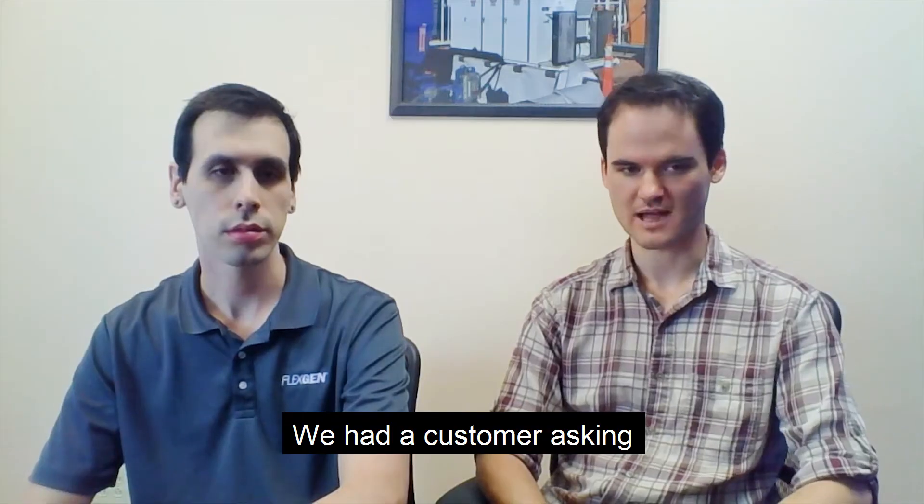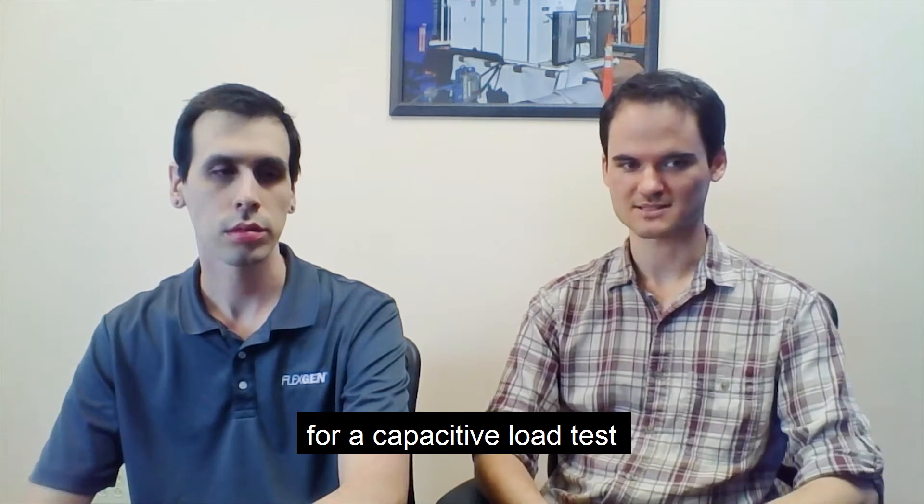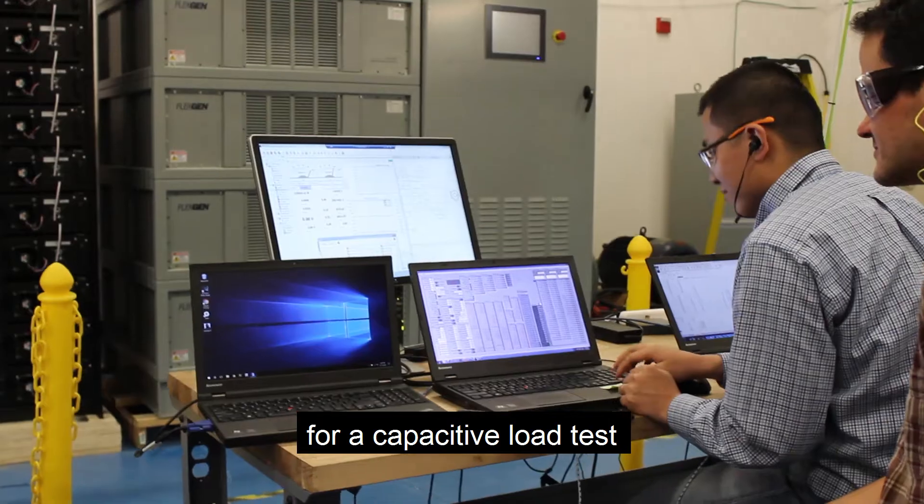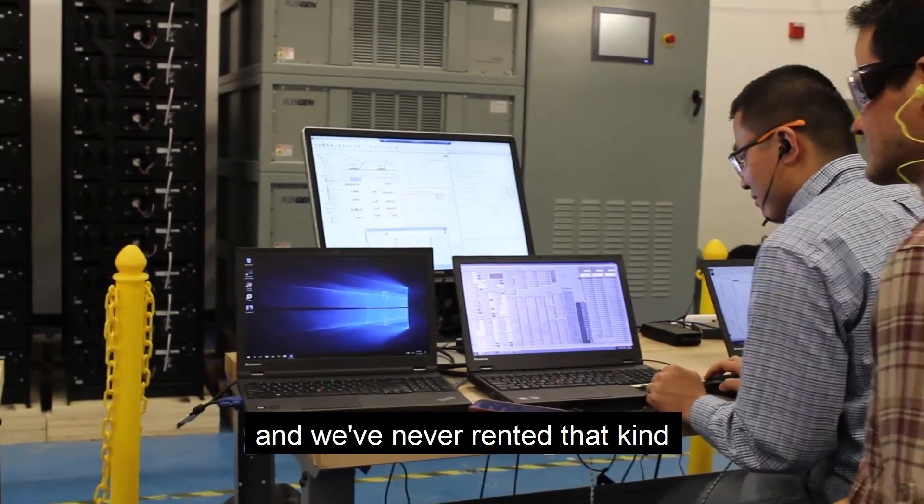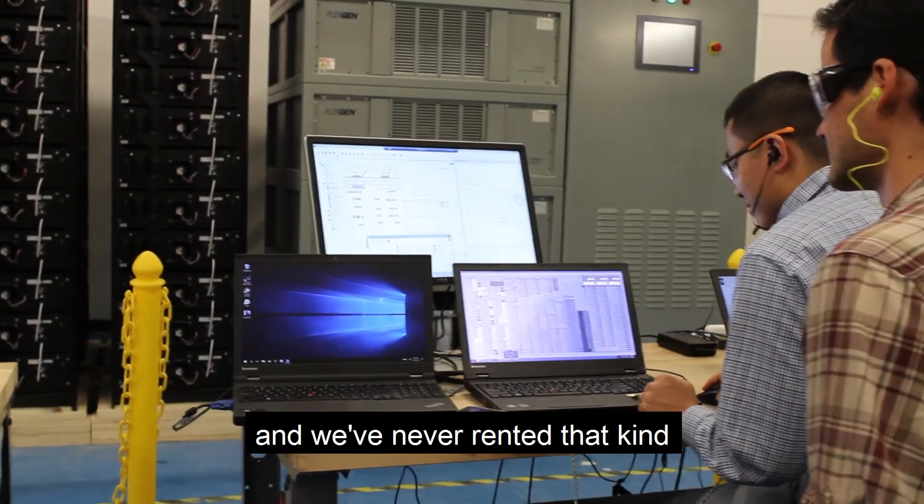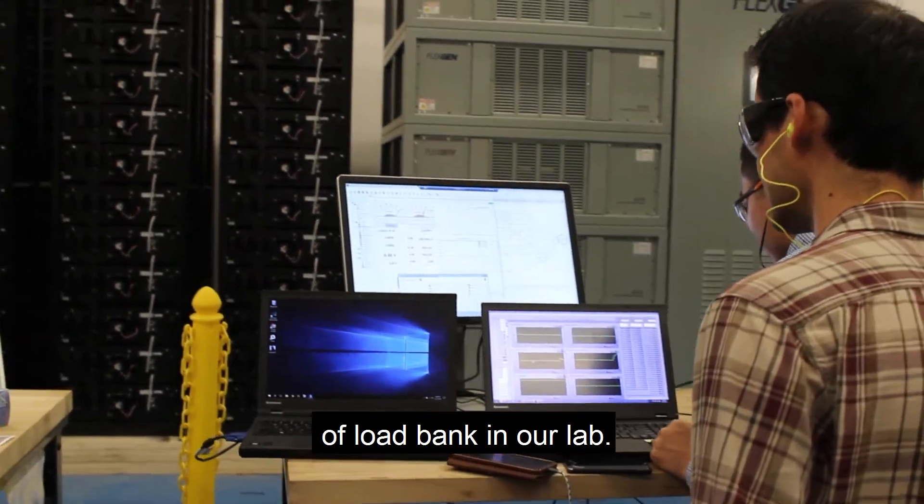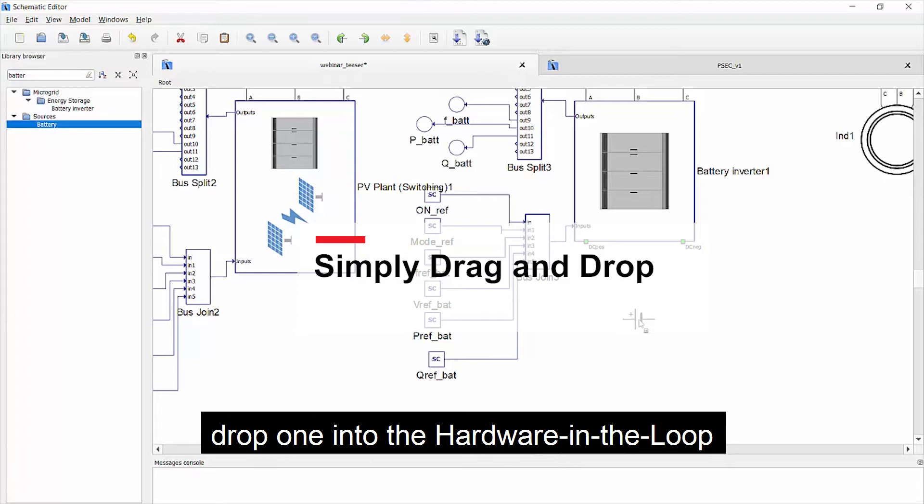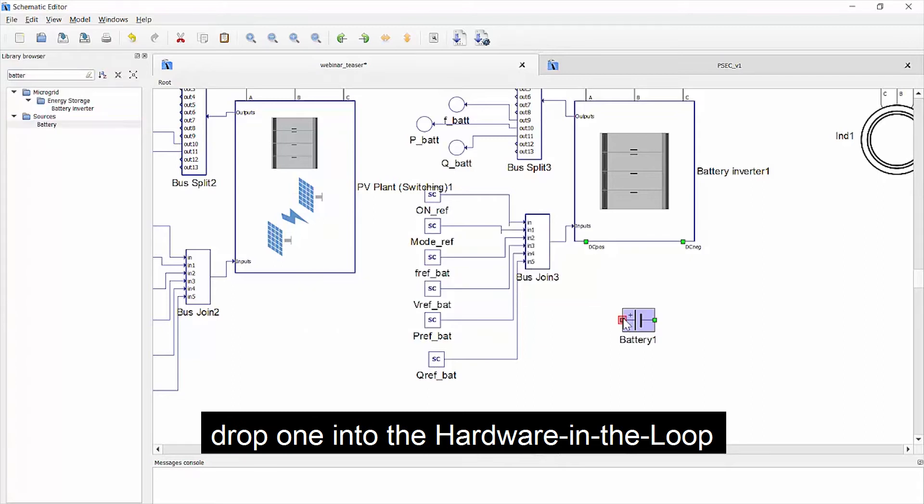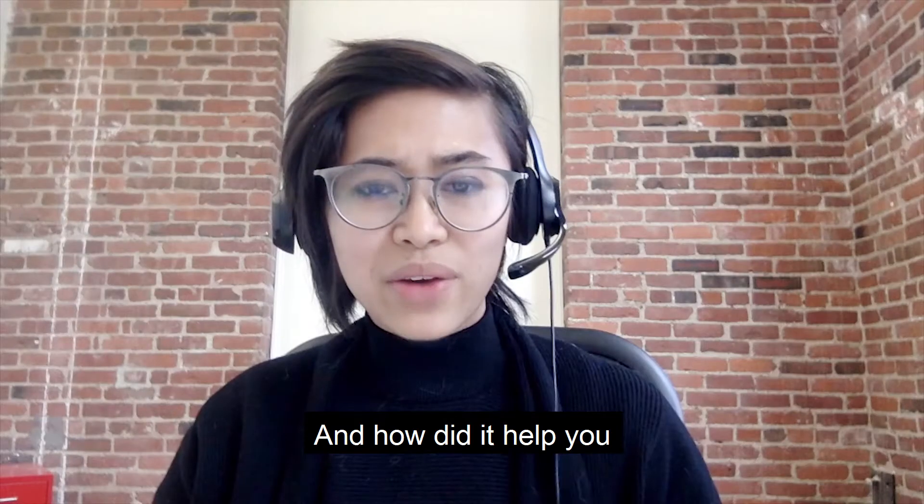We had a customer asking for a capacitive load test, and that was something we've never rented that kind of load bank in our lab. But we were able to just drop one into the hardware in the loop and then test it out there.